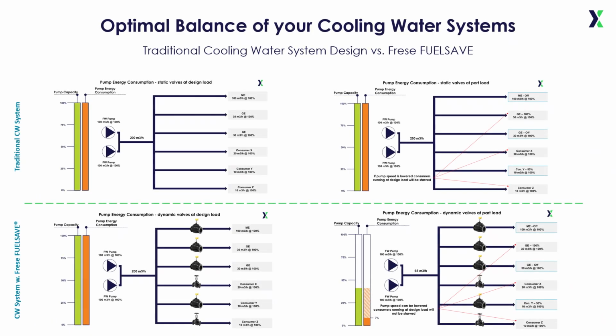This slide is a compilation of the 4 previous slides in one matrix. Above the green dotted line, we see the engine room fitted with static balancing valves. To the left at design load and to the right at part load. Below, we see the same system, but now equipped with pressure-independent valve technology. Again, to the left at design load and to the right at part load.